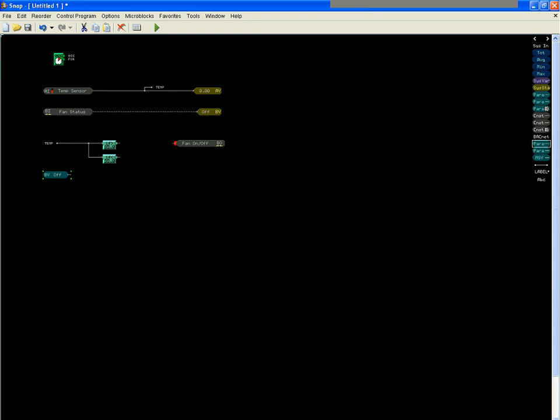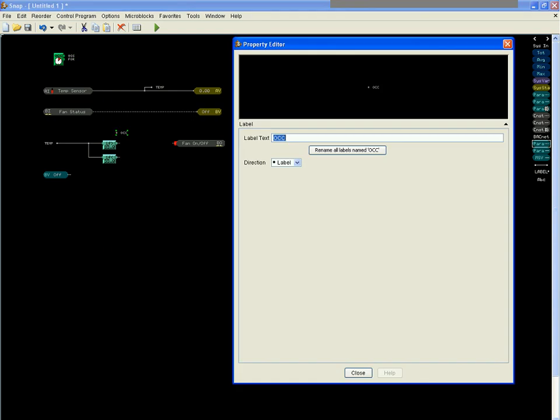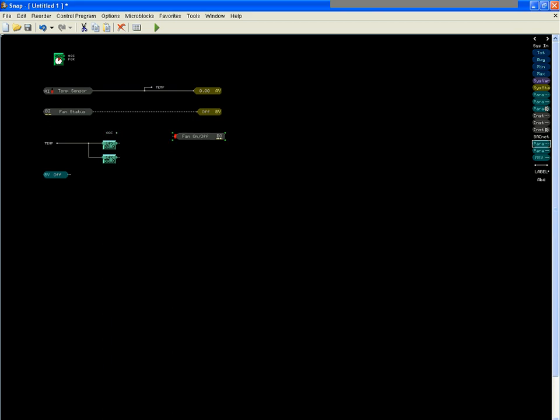The only reason I'm making it network visible now is because usually you want somebody to write to it. But those are default values, so you can change that as needed. And the last thing I want to do is take the label for occupancy. I'm going to put it down here because I want to control off occupancy also. So if it goes occupied, it's going to turn the fan on.